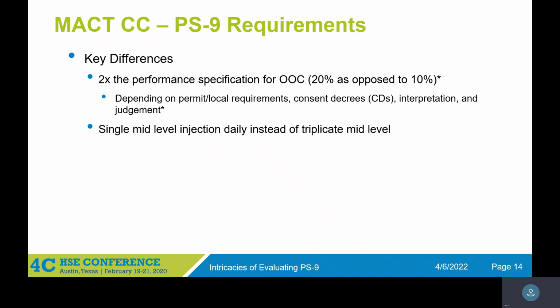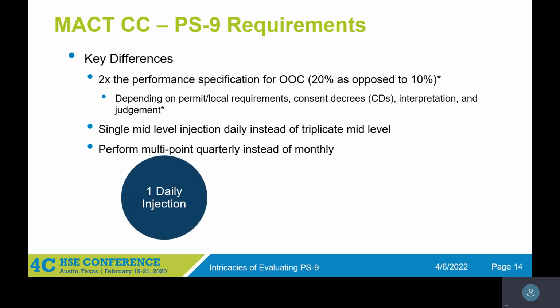So the other key difference is that single mid-level injection daily instead of the triplicate mid-level daily, and that multi-point quarterly instead of monthly. So one daily injection, and then compare that against your gas concentration, and make sure it's less than or equal to 20% error or 10%, depending on your own interpretation and requirements that you need to meet there.